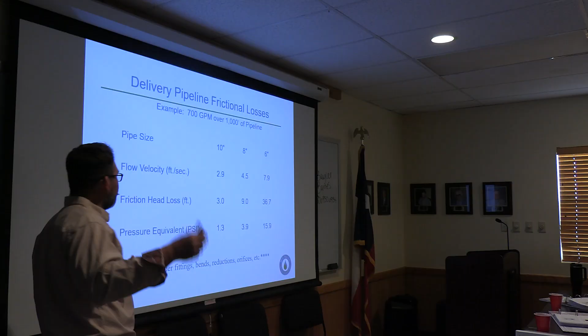Add up the friction, or look at the friction head losses from that. You can see if I go with the 8-inch, it's going to be 9 feet of friction loss. If I go to the 10-inch, it's much more subdued. And if I do the pressure equivalent, it's the equivalent to 4 psi versus 1.3 psi of loss. In this case, the major difference is between the 6 and the 8. So you definitely don't want to go with the 6, but you would have to really do a little bit of strategy to see, do I want the 10-inch, do I want the 8-inch in this scenario? In most cases, the economics, if you are looking at it on a 5-year horizon or less, is I want this 8-inch. If you're looking at it on a permanent horizon, you think this is my property for 40 years, I'm going to do it right the first time, you would go with the bigger pipe.